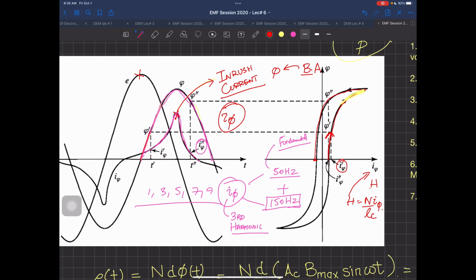This inrush current normally should have been a certain amount, but how much does it actually become? It is approximately 2 or 3 times. That 2 or 3 times current is producing a voltage drop, and that voltage drop is producing less voltage to your home.